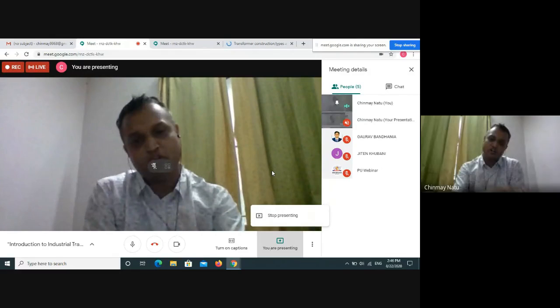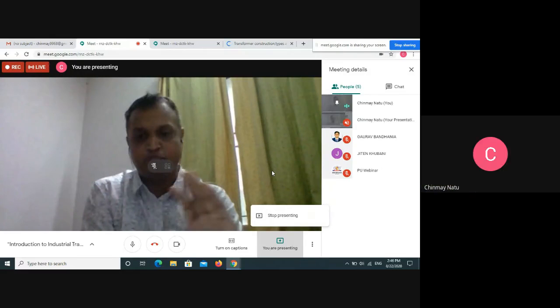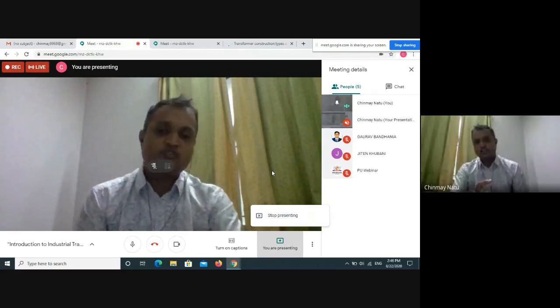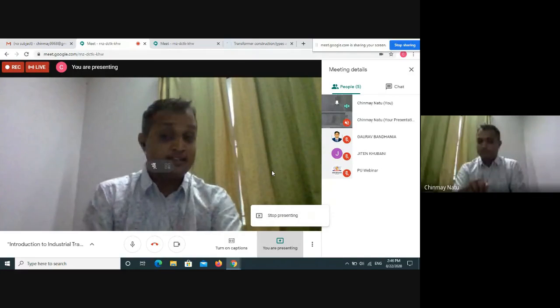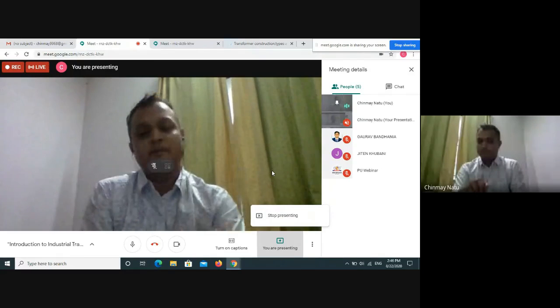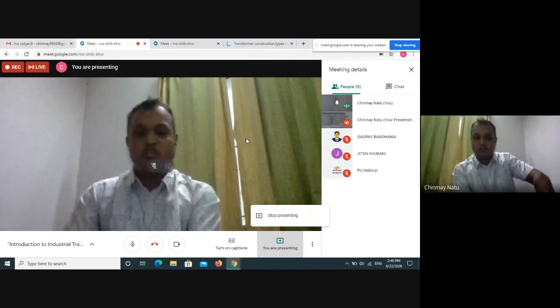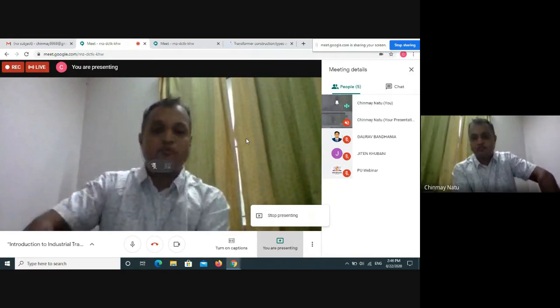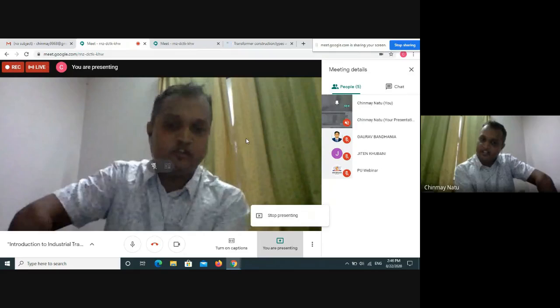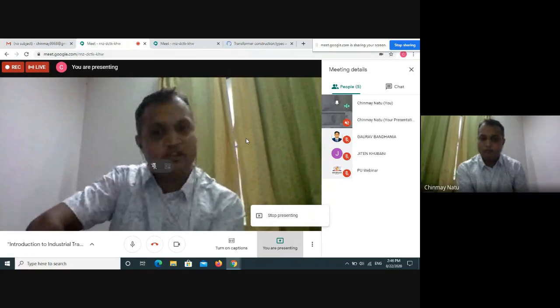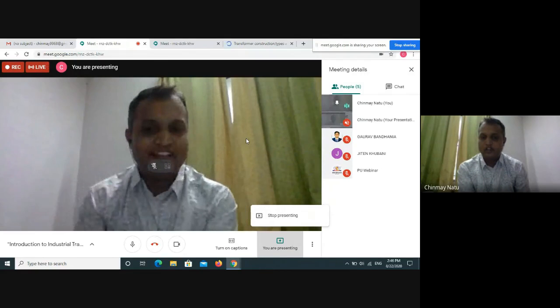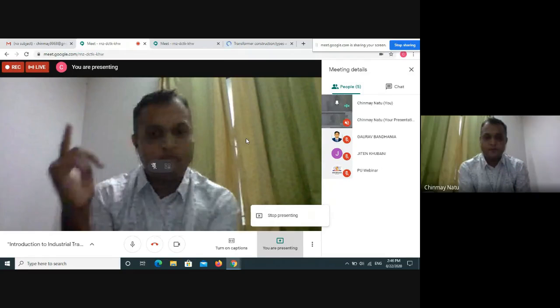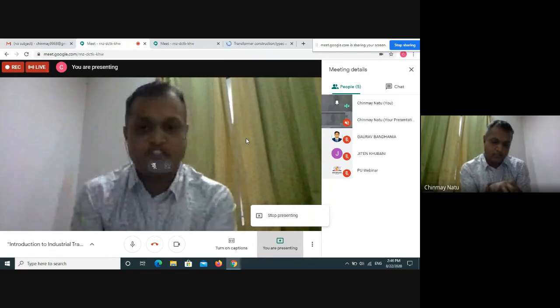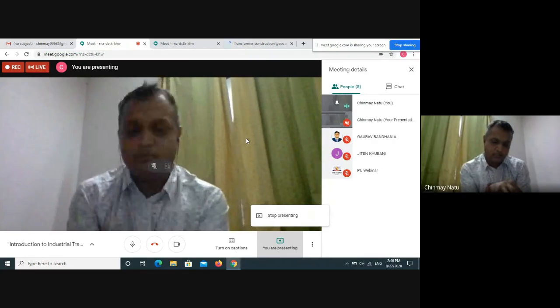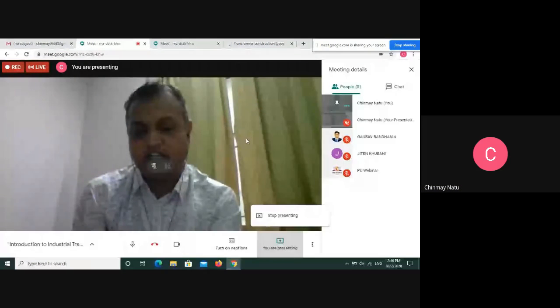Secondly, another transformer is used to create a neutral. This is a very typical question, most engineers don't know where the neutral comes from. Let me explain where the neutral comes from. The industrial transformer has a big role in that. When voltage comes from the substation, on the primary side there is a delta winding, as I explained in the previous slide, and on the secondary side there is a star winding.